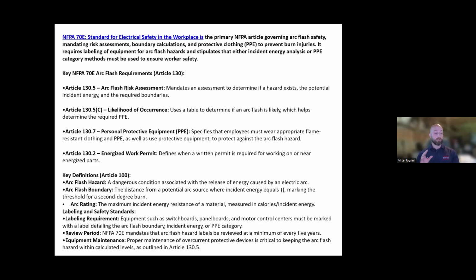To jump onto that, these labels also have a date in the bottom right on every single one of them. With the new code update, NFPA 70E mandates that the arc flash labels have to be updated. The arc flash short circuit coordination study has to be updated once every 5 years. Most buildings in Boston are constantly doing work, and the reason it's done every 5 years is that anything added to the building has to be captured and entered into the study, because the simplest install could greatly affect downstream of the actual study.